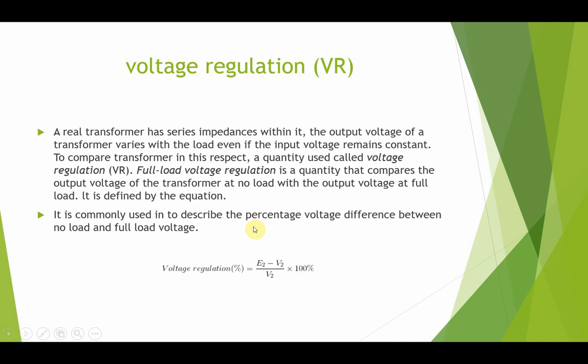Suppose we have a transformer with its secondary open, meaning no load is connected. The voltage at that point is the EMF induced in the secondary winding E2 — this is the no-load voltage. When we connect a load, there will be a voltage drop on the secondary side due to secondary current I2 and secondary impedance Z2, so the secondary terminal voltage V2 will be less than the no-load voltage. Therefore, voltage regulation equals E2 minus V2, divided by V2, multiplied by 100.